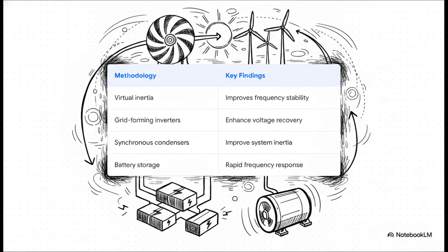By using advanced control loops in grid-forming inverters, they can actually program solar and wind farm inverters to mimic the exact behavior of a heavy spinning mass. They're also deploying battery energy storage systems for rapid frequency response. And in some cases, they're straight up installing synchronous condensers, which are basically massive motors that don't generate any power. They just sit there spinning to provide that missing physical inertia and voltage support.